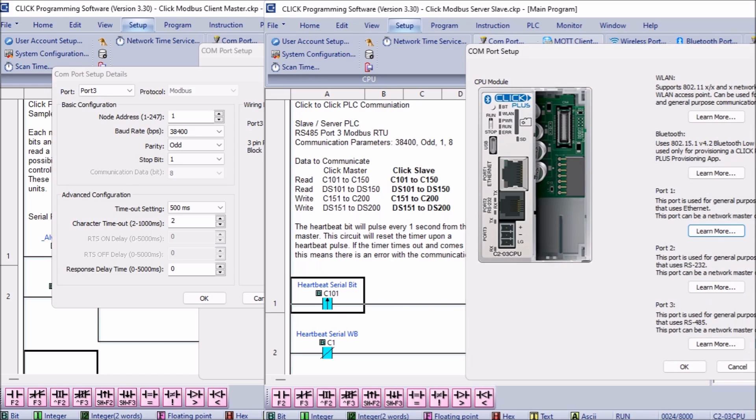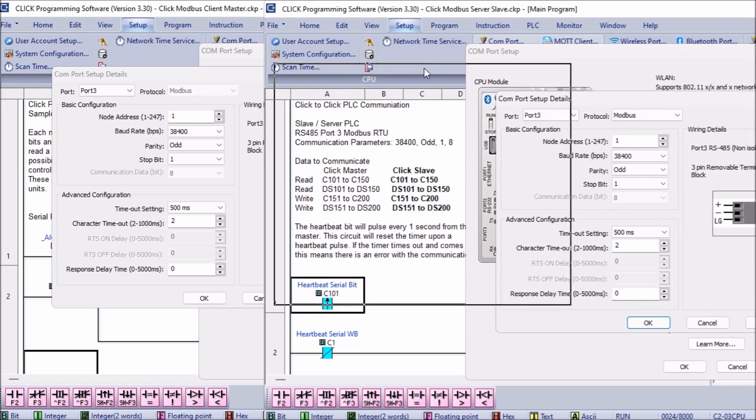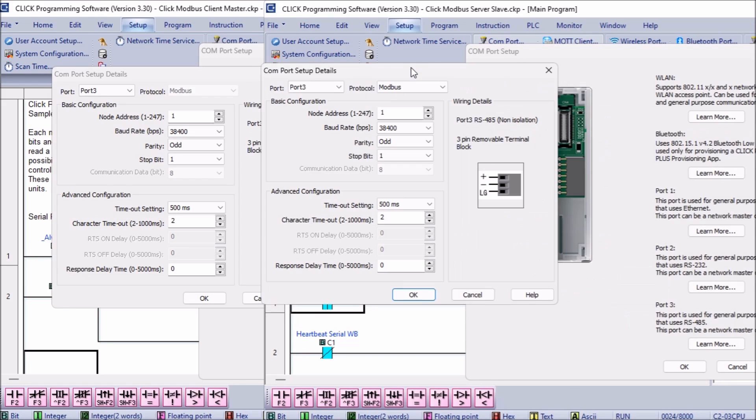The baud rate, parity, and stop bit communication parameters must match the master and the slave PLC settings. We are using the highest baud rate setting on the Click PLC.